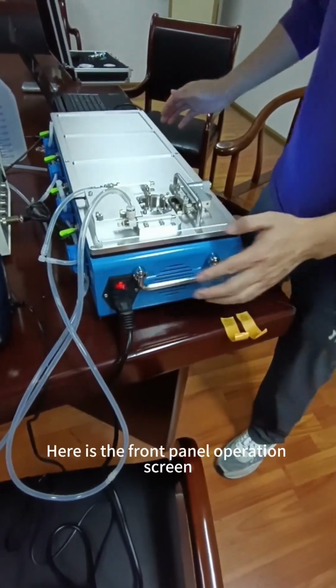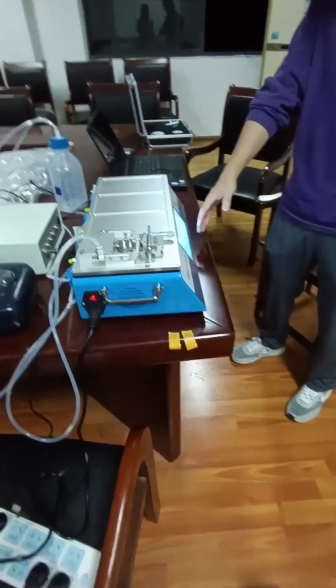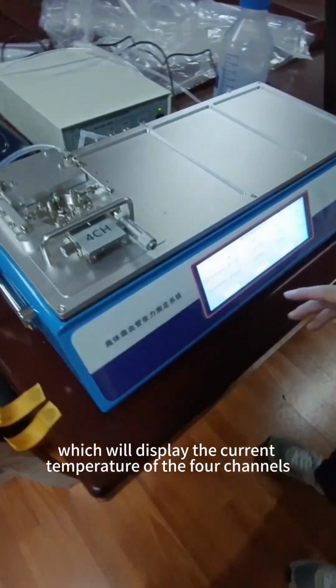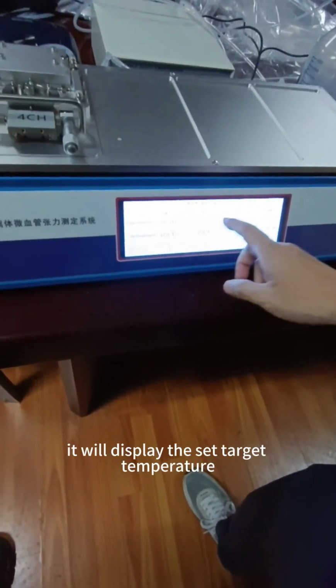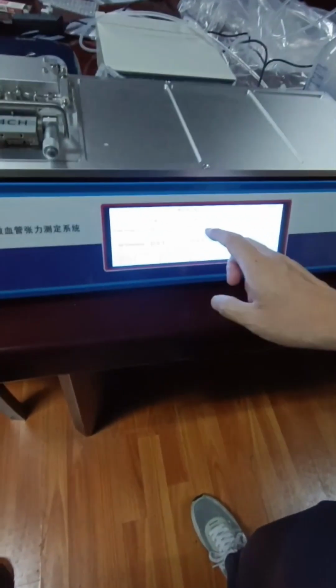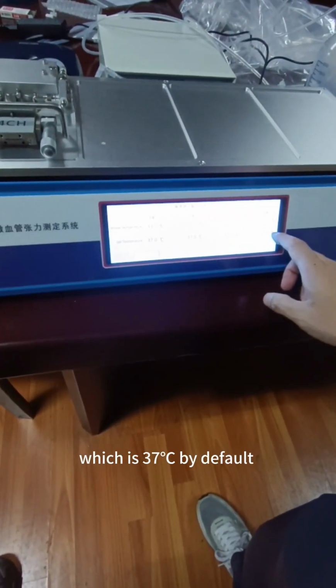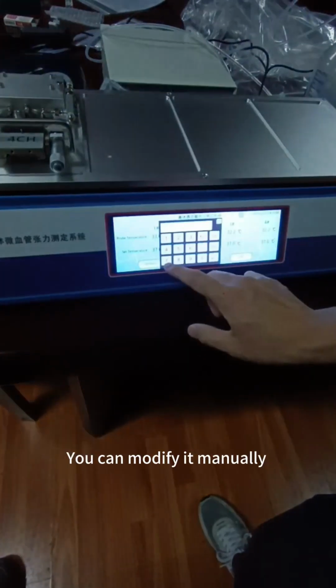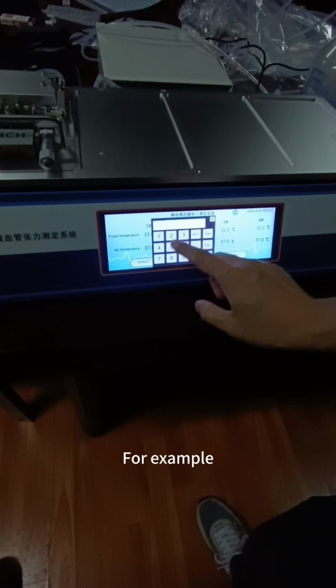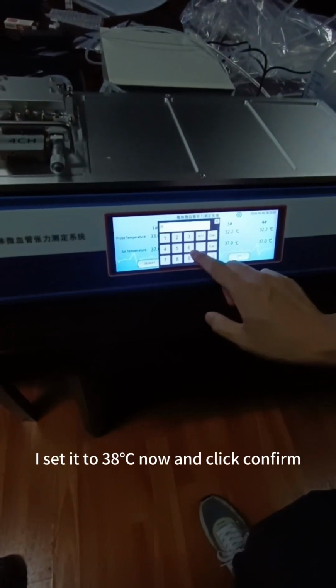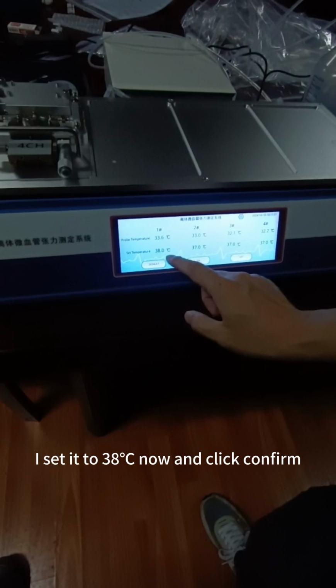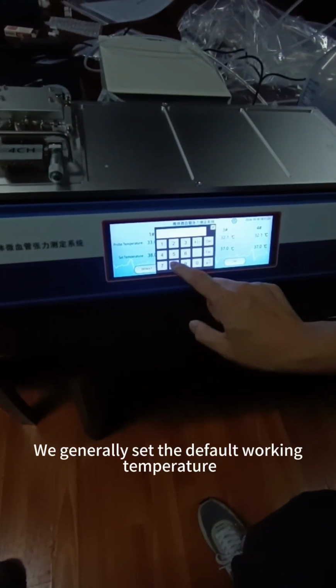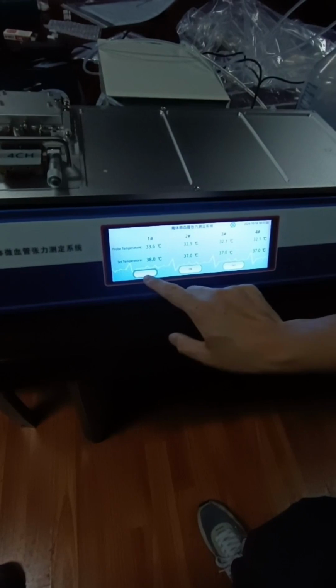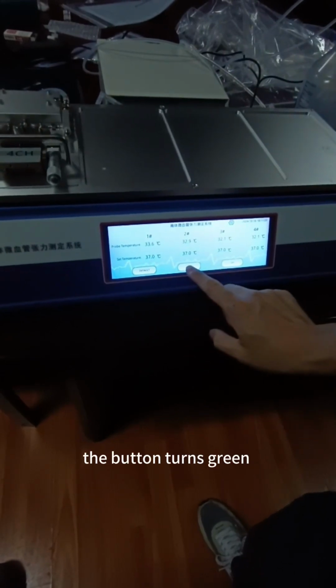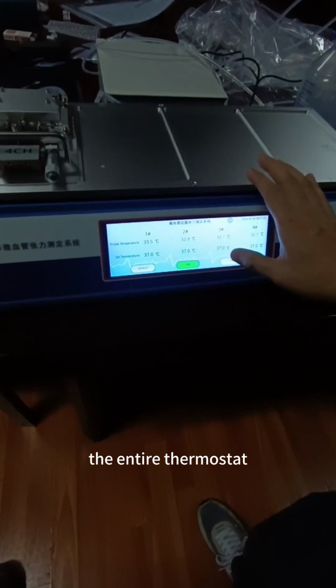After it lights up, here is the front panel operation screen, which will display the current temperature of the 4 channels. At the same time, it will display the set target temperature, which is 37 degrees Celsius by default. Of course, you can modify it manually. For example, I set it to 38 degrees Celsius now, and click Confirm. We generally set the default working temperature to 37 degrees Celsius. The button turns green. At this time, the entire thermostat starts working.